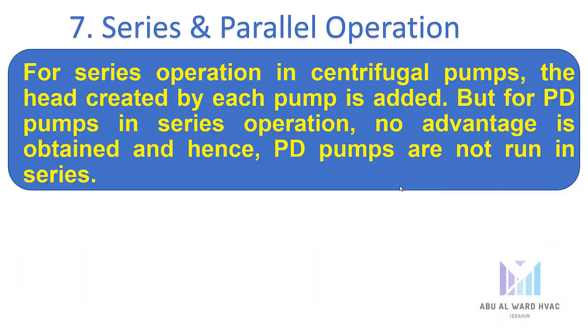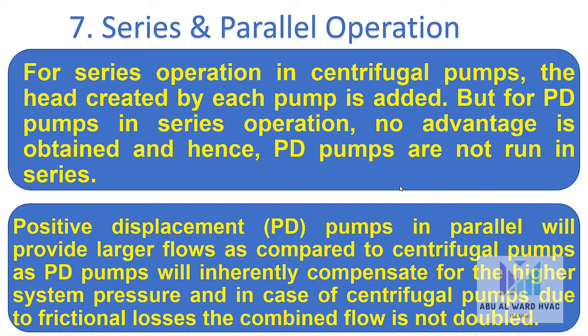For series operation in centrifugal pumps, the head created by each pump is added. For positive displacement pumps in series, no advantage is obtained, so positive displacement pumps are not run in series. In parallel, positive displacement pumps provide larger flows compared to centrifugal pumps, as they inherently compensate for higher system pressure. In centrifugal pumps, due to frictional losses, the combined flow is not doubled.